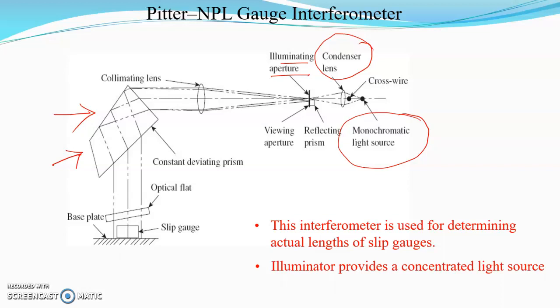The user can select a particular color by tilting the angle of the constant deviating prism. For a particular angle, it will give a particular light ray of a particular wavelength.